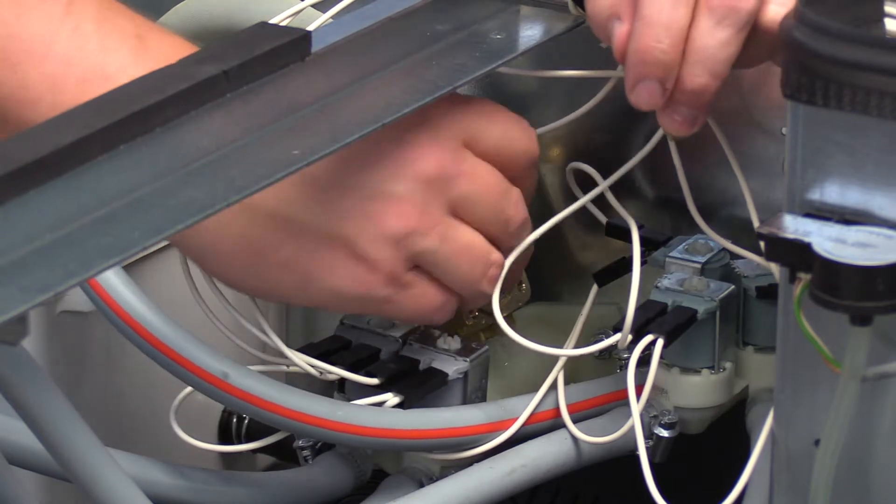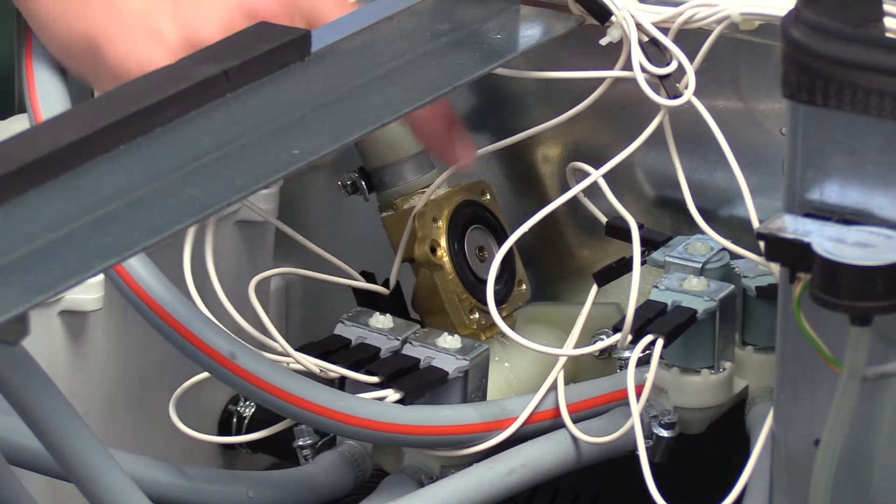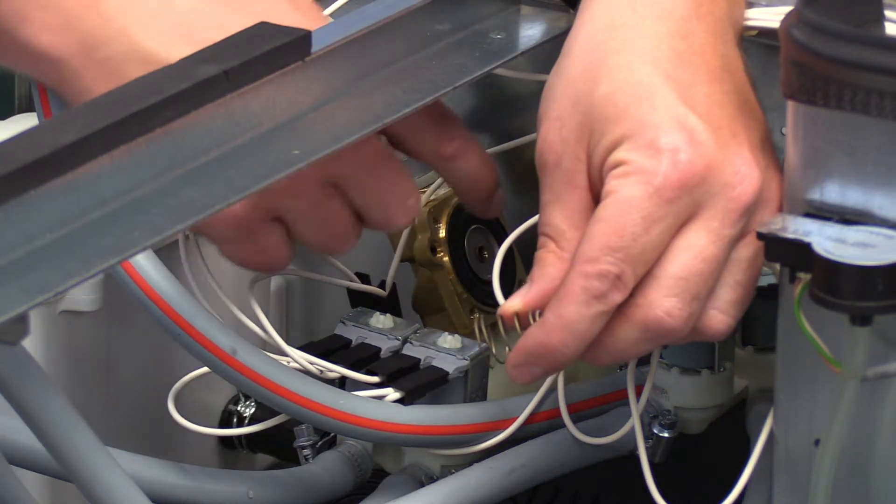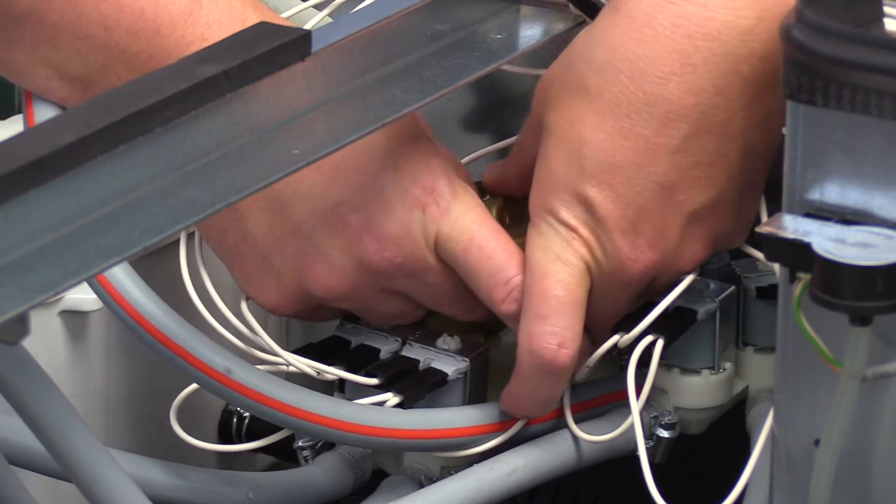Reinstall the rubber diaphragm with the equalizing orifice on the valve. The concave part of the diaphragm will face out. Place the spring on top of the diaphragm with the wide end of the spring centered on the diaphragm.